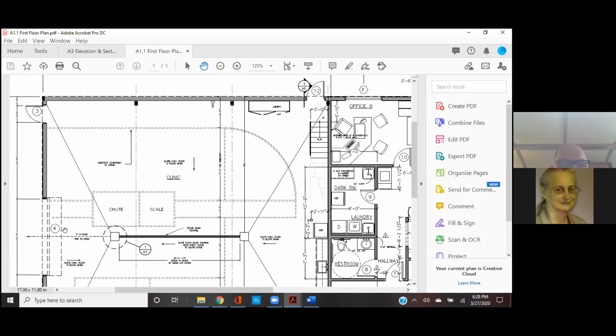And then you might even have, like you said, a curtain going across there, maybe two vents or something. No, I would actually have something called a hot air curtain. It's a long, thin supply that drops hot air down like a curtain, and that keeps cold air out. It won't stop wind, but it stops that sudden rush of cold air in.